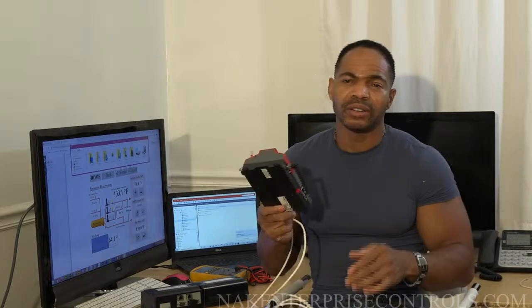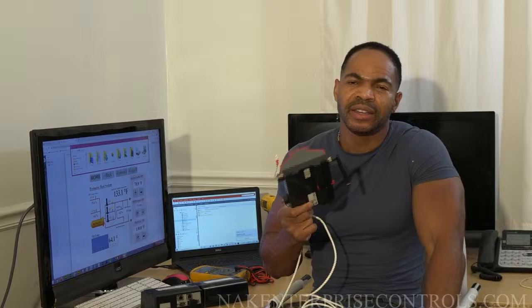Years ago, we had controllers that were on a network. You had a main controller, and then the other controllers didn't contain a brain, they didn't contain any sort of actual functions. They were simply taking everything from the main. So if the network got cut, you would have units just go right down. And that was a big problem.